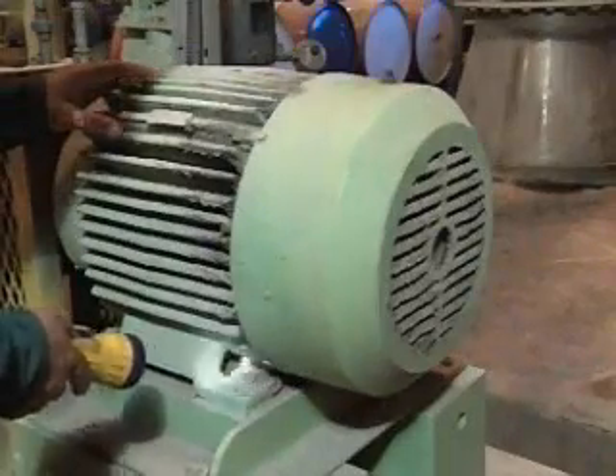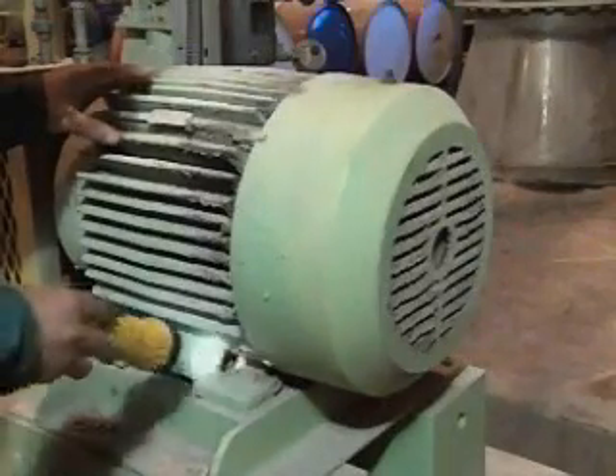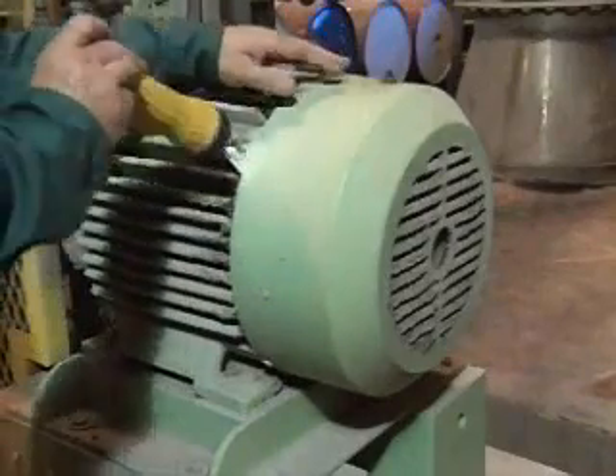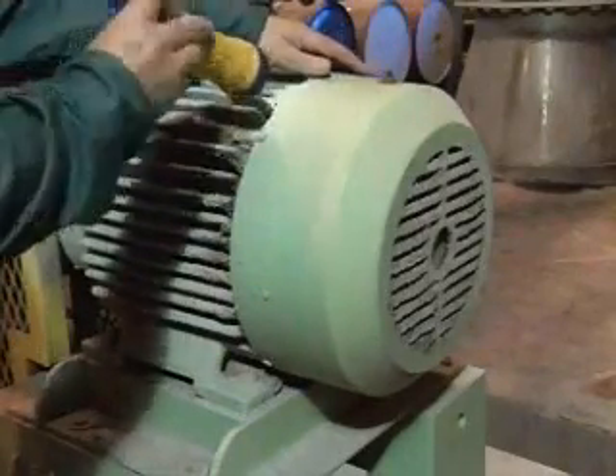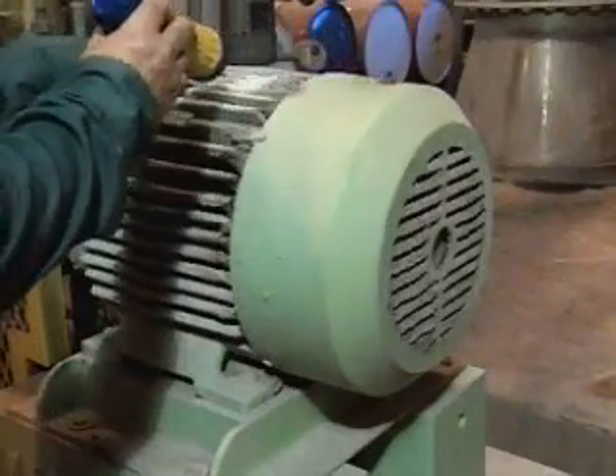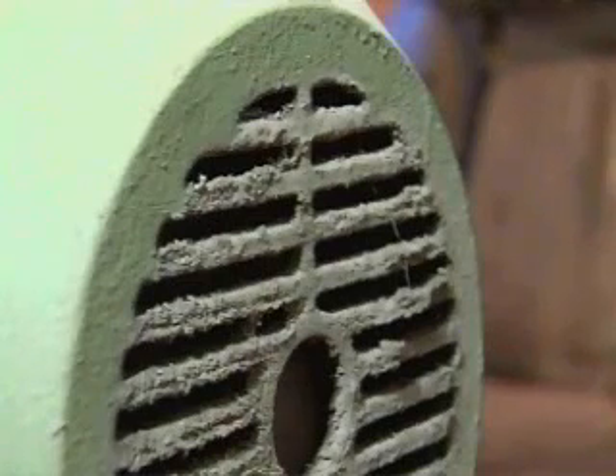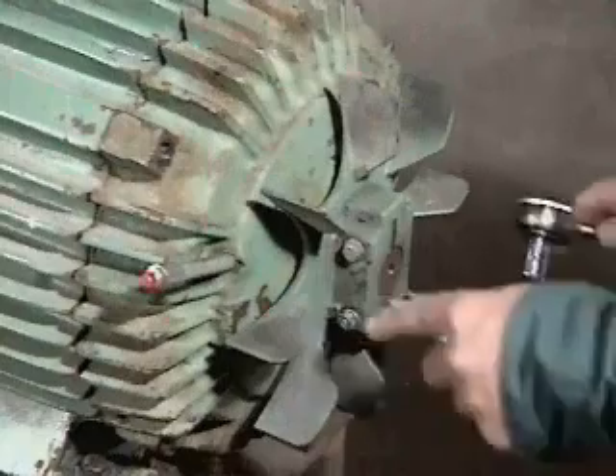There are three types of motor maintenance. Preventive motor maintenance is maintenance that is done on a routine basis in the field with no disassembly of the motor. The purpose of preventive maintenance is to maintain the motor, clean the exterior parts, lubricate accessible parts, make minor adjustments, and identify potential problems.